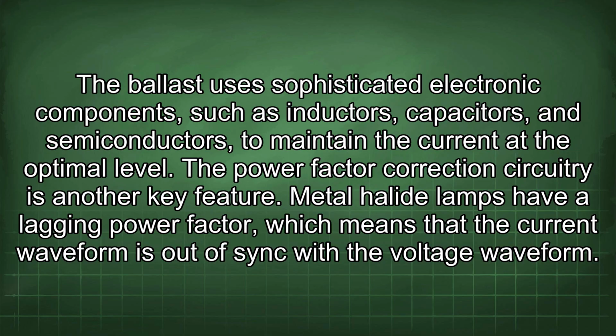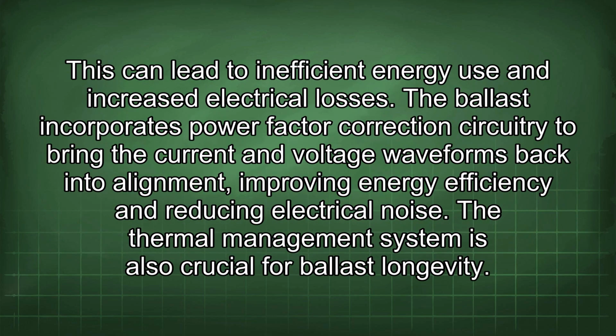Metal halide lamps have a lagging power factor, which means that the current waveform is out of sync with the voltage waveform. This can lead to inefficient energy use and increased electrical losses. The ballast incorporates power factor correction circuitry to bring the current and voltage waveforms back into alignment, improving energy efficiency and reducing electrical noise. The thermal management system is also crucial for ballast longevity.